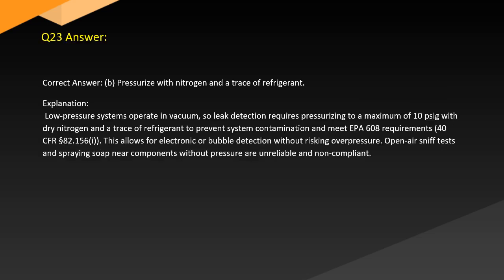Answer. Correct answer, B. Pressurize with nitrogen and a trace of refrigerant. Explanation. Low-pressure systems operate in vacuum, so leak detection requires pressurizing to a maximum of 10 psig with dry nitrogen and a trace of refrigerant to prevent system contamination and meet EPA 608 requirements, 40 CFR 82.156. This allows for electronic or bubble detection without risking overpressure. Open-air sniff tests and spraying soap near components without pressure are unreliable and non-compliant.